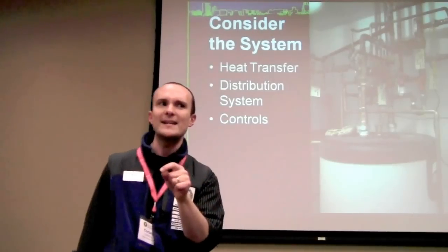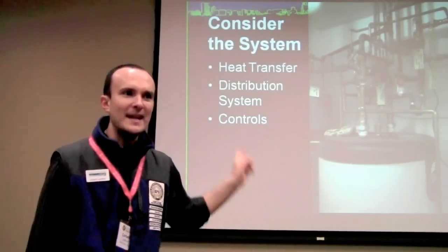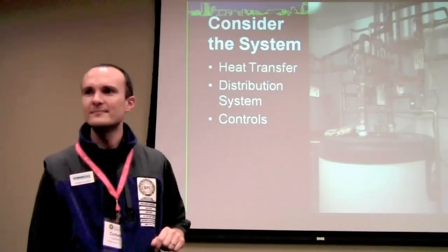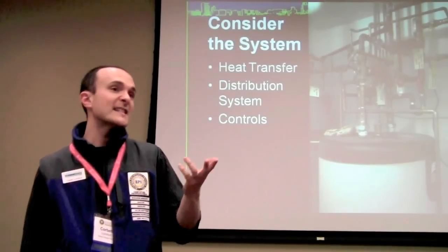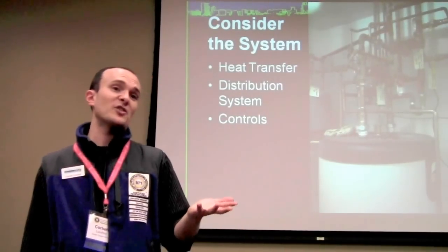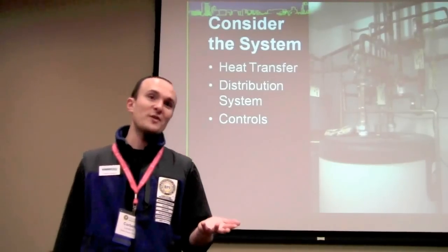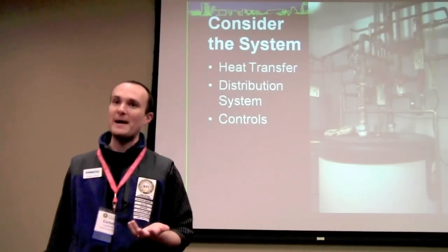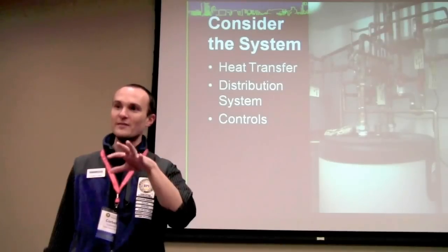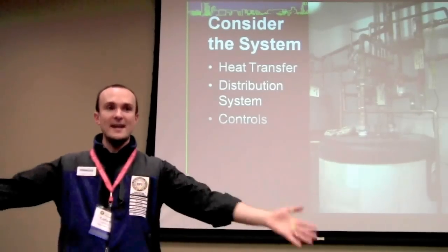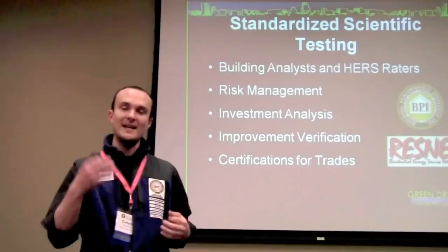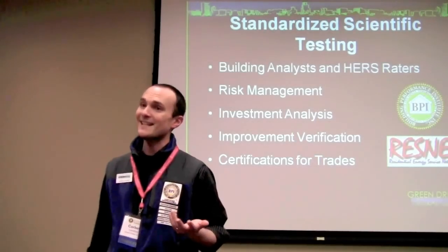Where would you not want any insulation in a mechanical system? Around, let's say, outside on the condenser coil of the air conditioner. Did you know dust actually has a really huge impact on heat transfer? The whole goal of the air conditioning coils is to give off heat to the outside or soak it in from the inside, and anytime you've got dust on it, it acts as an insulator.